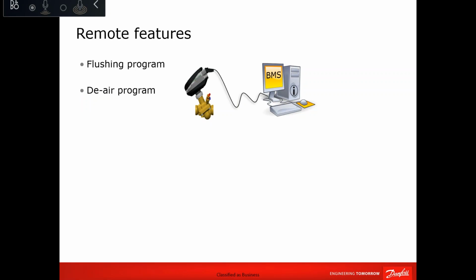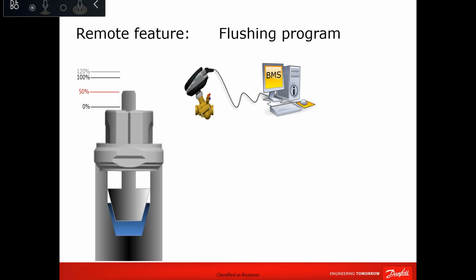So flushing and de-air. Okay, if we already set the flow to 50%, since we allow the forward and backward flushing through the valve, we can flush our valve to clean your coil. So to do the flushing, we recommend the valve should be at full open position.